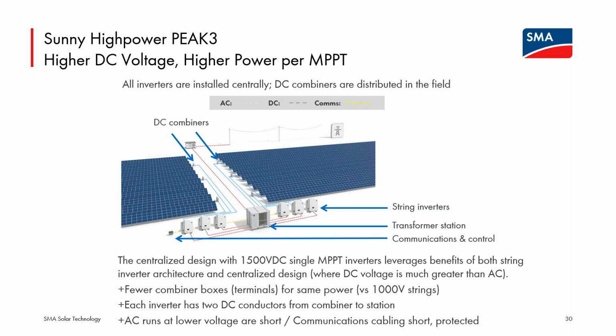But we generally would suggest, even with the PEAK3, where you have smaller power conversion units, to have as many of those units as possible be centrally located. The reason is that even for the 150 kilowatt unit, the AC or output side voltage is 600 volts, where the DC input voltage side should be much higher. So having very long runs at the higher voltage, you will have lower line losses for transmitting the power. So generally, it's much better to have the DC conductors go a long distance versus the AC conductors.